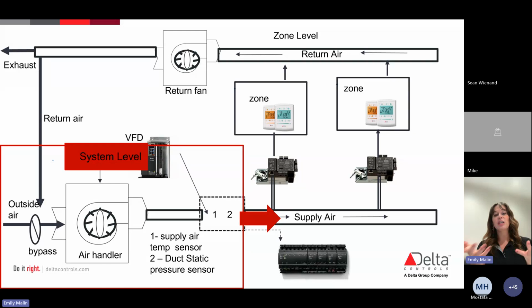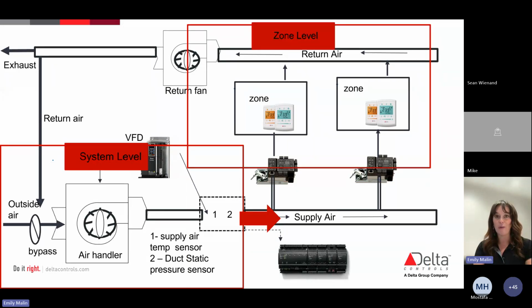And this is actually getting triggered by our zone level. So again, we have these set points in each one of our zones, and we want to maintain those. And so when something is out of that set point, you're getting a request, and that request is going to say, hey, we need more air in zone 1, or we need less air in zone 2. And what that's going to do is dictate how much air is actually going through that duct, right? And then obviously we have the return fan, and then your air gets sent through. But what's important to note here is that what's changing is just the amount of airflow to and through those VAV boxes to the zone.